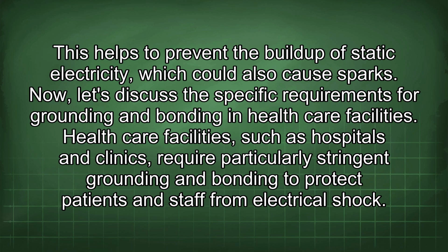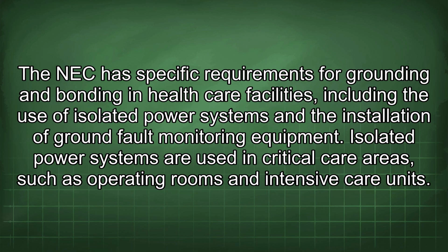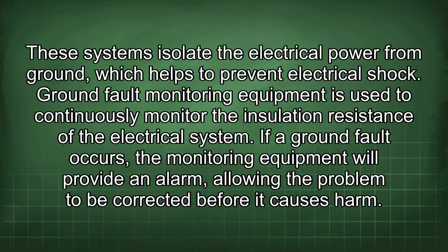Now, let's discuss the specific requirements for grounding and bonding in healthcare facilities. Healthcare facilities, such as hospitals and clinics, require particularly stringent grounding and bonding to protect patients and staff from electrical shock. The NEC has specific requirements for grounding and bonding in healthcare facilities, including the use of isolated power systems and the installation of ground fault monitoring equipment. Isolated power systems are used in critical care areas, such as operating rooms and intensive care units. These systems isolate the electrical power from ground, which helps to prevent electrical shock. Ground fault monitoring equipment is used to continuously monitor the insulation resistance of the electrical system. If a ground fault occurs, the monitoring equipment will provide an alarm, allowing the problem to be corrected before it causes harm.